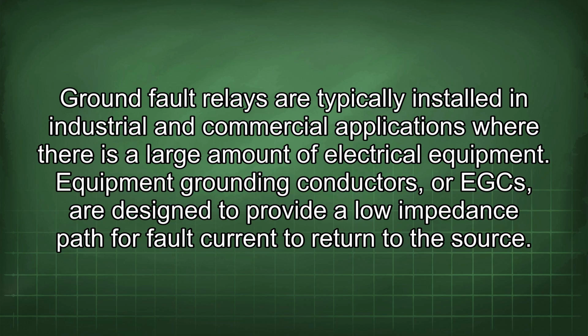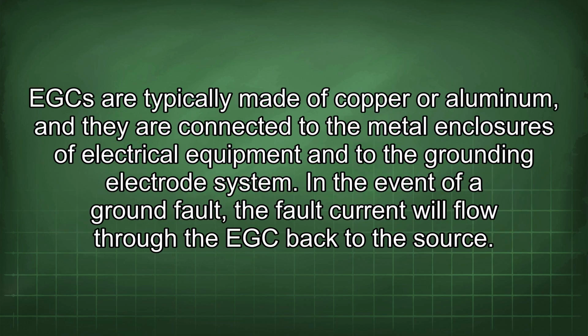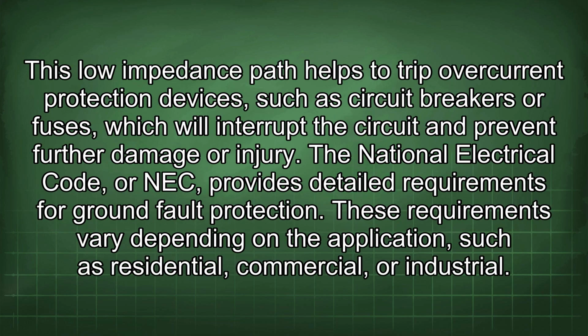Equipment grounding conductors, or EGCs, are designed to provide a low impedance path for fault current to return to the source. EGCs are typically made of copper or aluminum, and they are connected to the metal enclosures of electrical equipment and to the grounding electrode system. In the event of a ground fault, the fault current will flow through the EGC back to the source. This low impedance path helps to trip overcurrent protection devices, such as circuit breakers or fuses, which will interrupt the circuit and prevent further damage or injury.